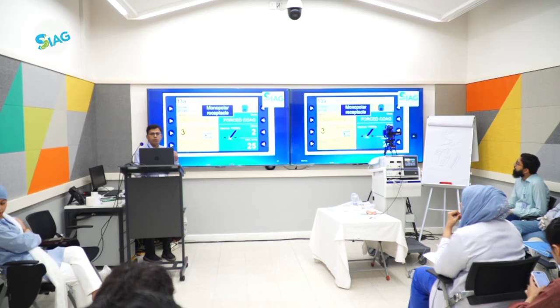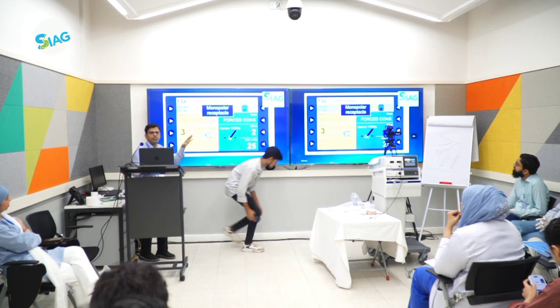So this is the screen of an ERBE electrosurgical unit. As most of us are moving towards ERBE, it's important to understand. It has two modes. The Q mode is used for snare, and I mode is used for sphincterotome.